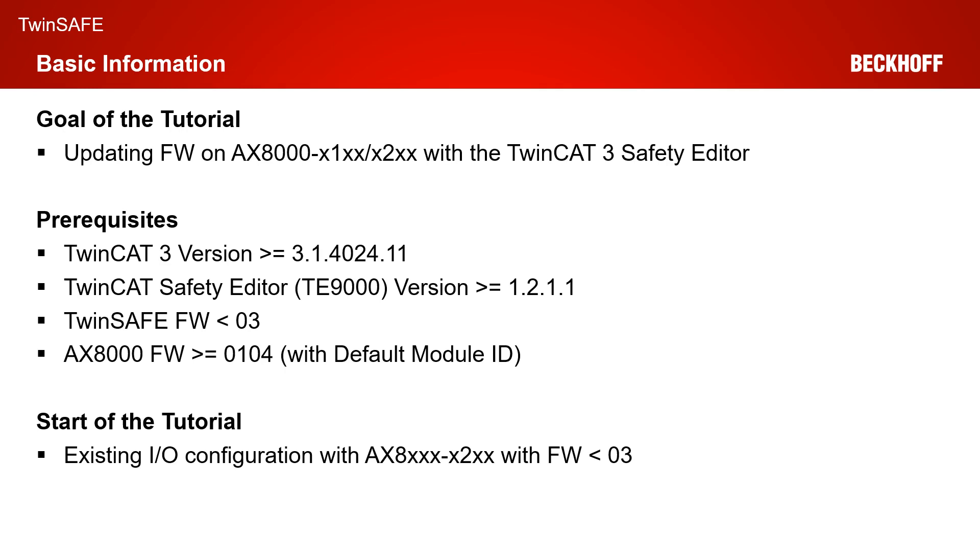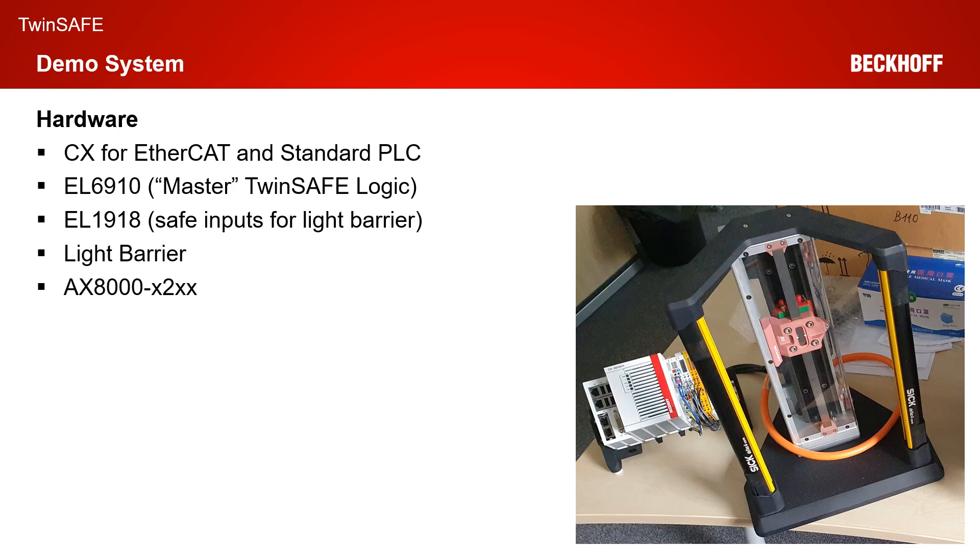This time you need a TwinSAFE firmware less than 03 because of course we want to do an update to 03, and you need an AX8000 firmware greater or equal to 0104 with the default module ID active. The start of the tutorial is an existing I/O configuration with an AX8000 X2XX with a firmware version less than 03. In our case, it's firmware 01.